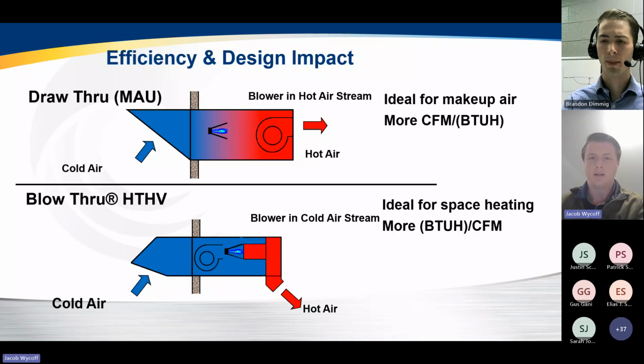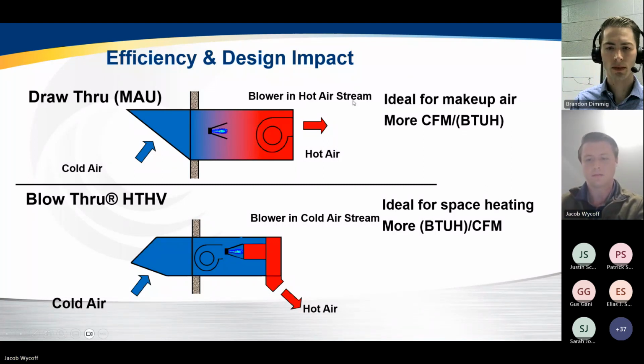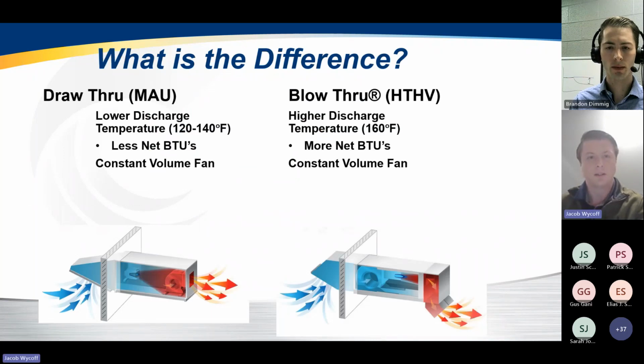Where HTHV becomes very efficient and a great application is whenever you're using it primarily for space heating. With that burner moved downstream of the blower, you're able to increase that discharge temperature to 160 degrees, like Brandon said, which is going to allow you to provide more BTUs and less CFMs. So our goal in that is to provide minimum amounts of ventilation while being able to provide large amounts of high efficiency direct fire heat into the space. So what's the difference between the two? We've already spoken about how the discharge temperature has a great effect on the amount of net, or usable, BTUs that you're providing to the space.